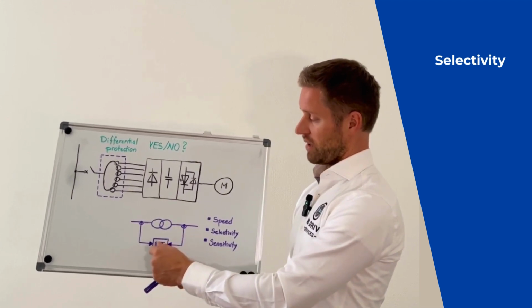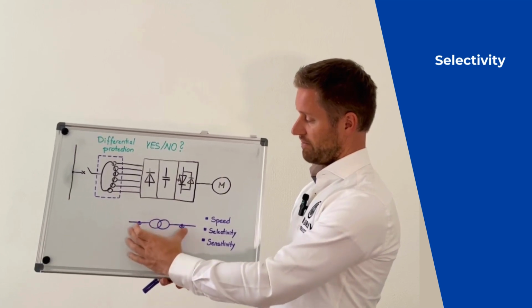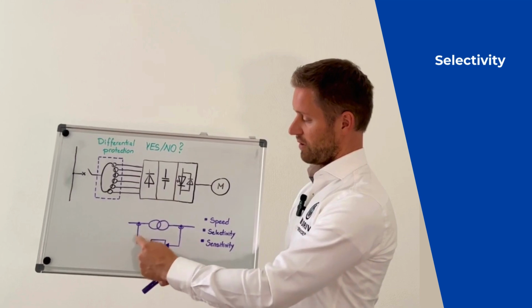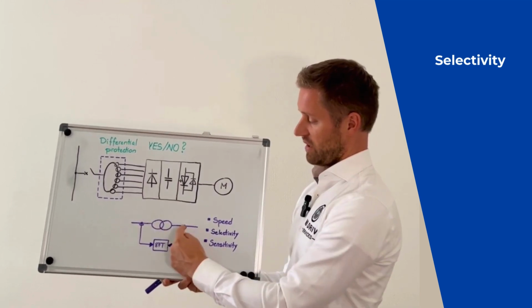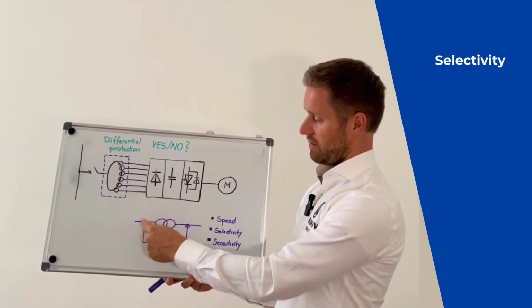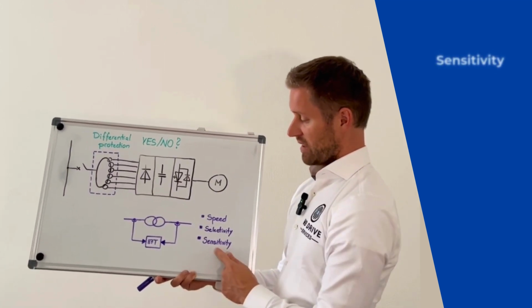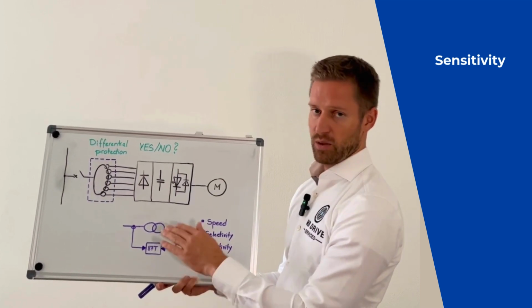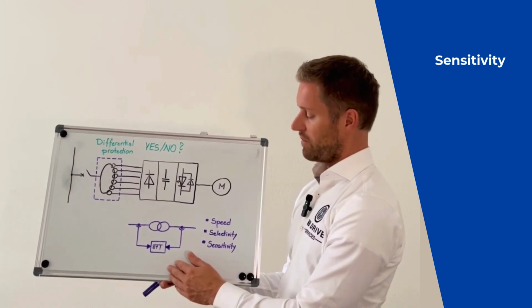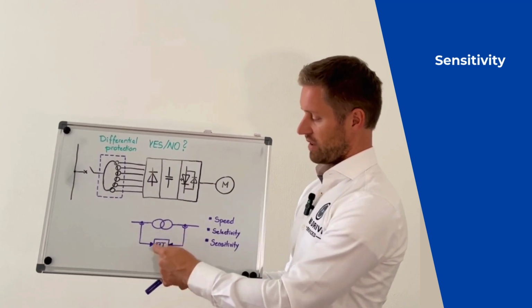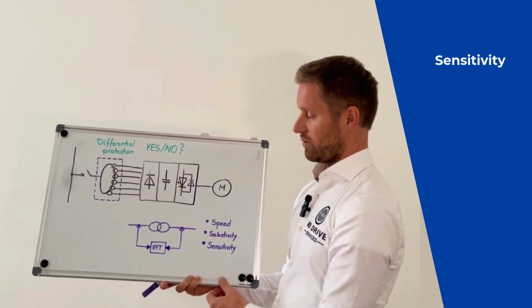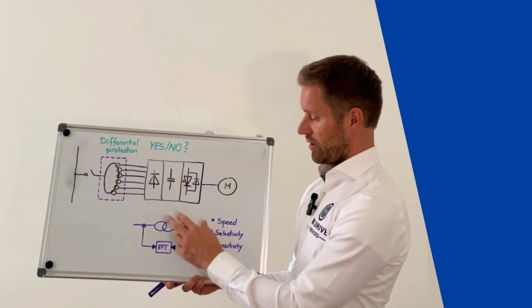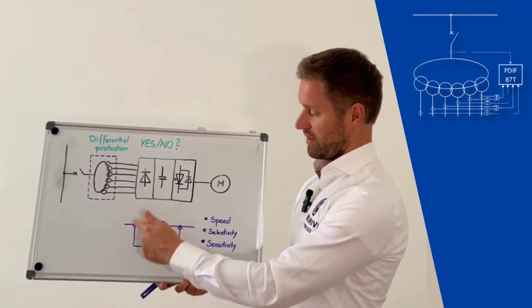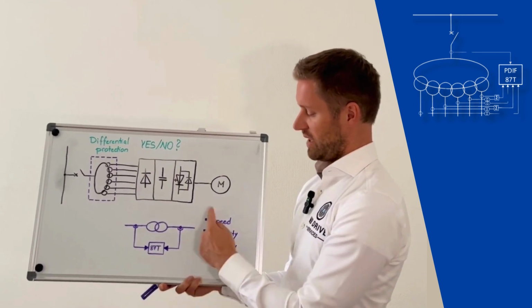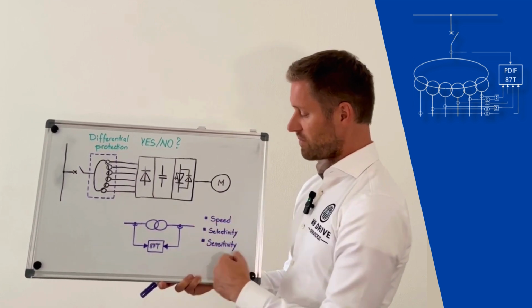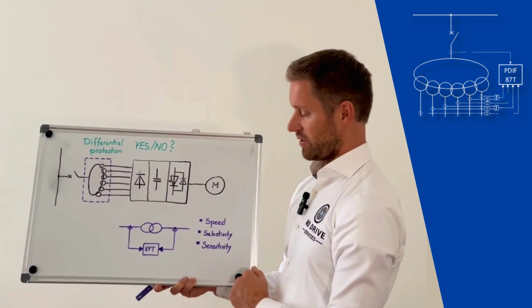Selectivity is basically the protection zone where the protection function is active. So for differential protection, the delimitation of the protection zone is by the measurement points on the primary and secondary side. So differential protection is active in between those two measurements. And sensitivity is about the threshold where the protection function picks up, so in this case, the error in the current that causes the protection reaction. So on a simple transformer design, at least simple with regard to the number of windings, these are the superior characteristics where differential protection excels.